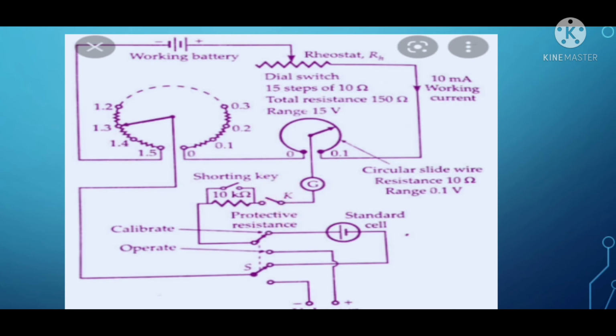Initially the entire circuit comes into operation under the calibrated position. The amount of voltage entering is positioned by means of these two switches, and at that point we can standardize the instrument.